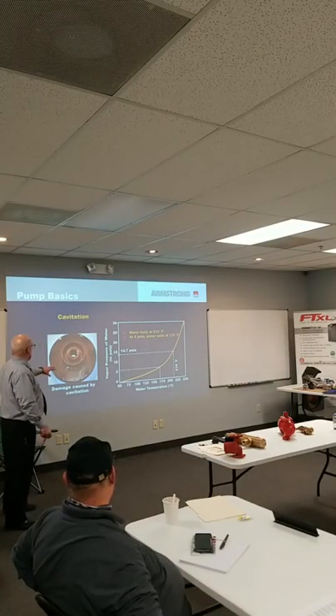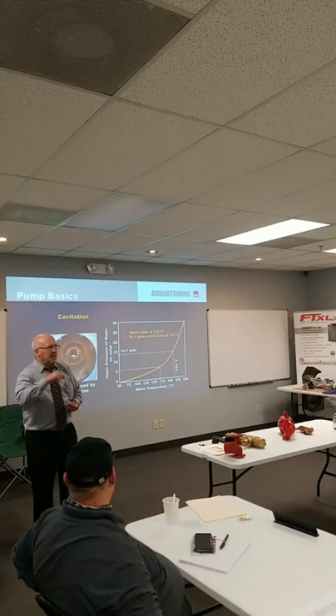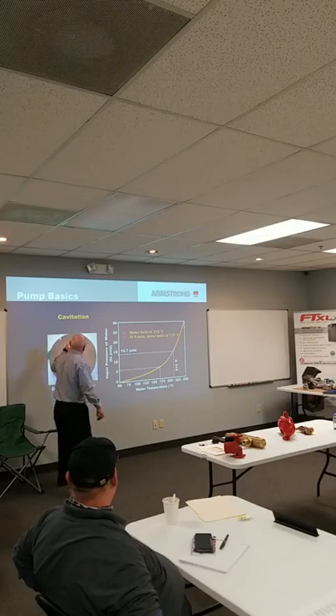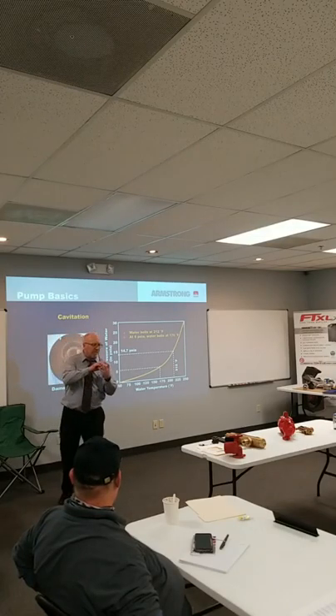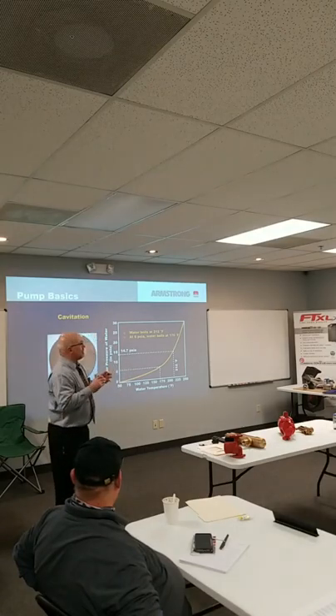I've seen impellers that were just pitted, like somebody took a drill and put little 16th-inch holes all over the impeller. What happens is, as the water goes into the eye, all of a sudden the impeller imparts pressure to it, and then it goes from 1,600 times to 1. And that's where the damage is, and that's where the noise is.